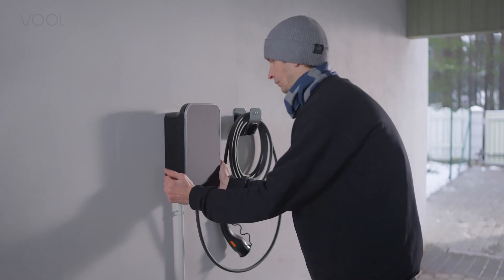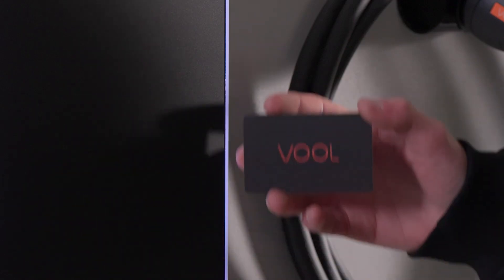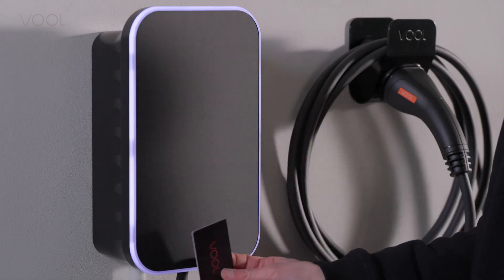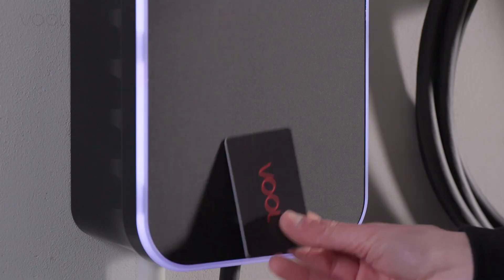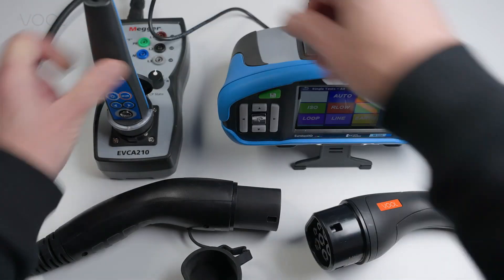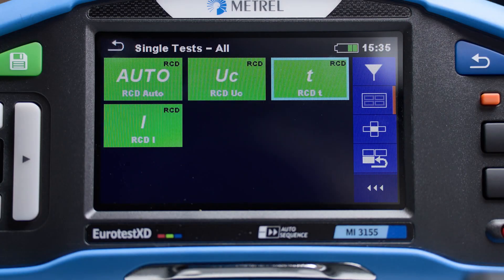Finally, snap on the front panel and make sure all six snaps click in. In case you need to set up an RFID card, you can do it on the VOOL Portal. You can use any compatible RFID card. When setup is done, perform an RCD test on the charger to validate that the circuit works correctly.